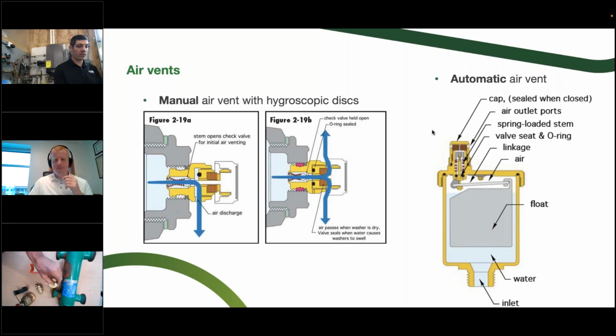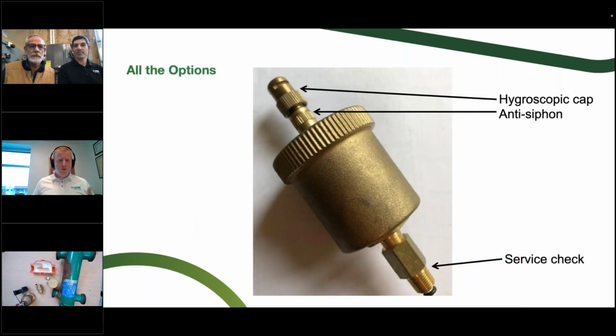But like Cody said, if you don't collapse the air pocket there and there's not debris in the top, it may never happen. But I know that every contractor on the call has probably seen an air vent that is leaking a little bit at some point in the year. It's also a great way to prevent the redecorating of floors with soggy ceiling tiles and things like that. So if it's above a hallway or something like that, that great little cap is pretty awesome.